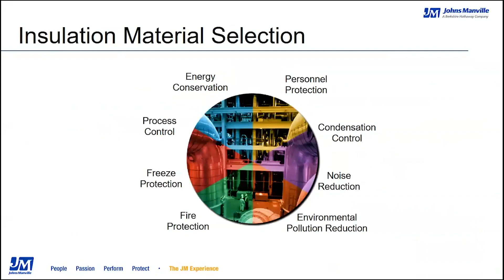The second one would probably be noise reduction or acoustical control, making sure that the occupied spaces you're limiting and mitigating the sound from either fan noise or crosstalk through rooms or ducts as that sound reverberates and bounces down that ductwork, and making sure you have a conducive and quiet environment in that occupied space. The third one is also probably condensation control, and that's making sure in high humidity situations or you have vapor barriers that are put on your ductwork to be able to control that condensation depending on what application or where you're at and how those ambient temperatures affect the duct, regulate and help that temperature come down that system.